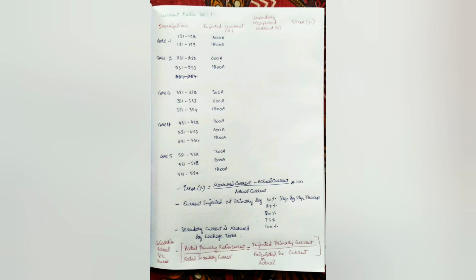So in the ratio test, for core 1 and core 2, S1 and S2 point is 600 amps maximum, and for S1 and S3 it is 1200 amps maximum. As per the connections, we will use the loading transformer for boosting the current, and then inject the current up to 1200 amps. So we inject some amps and then measure the secondary current, and that measured secondary current should be within the error percentage of your actual current level. For core 3, core 4 and core 5, as per the nameplate details: S1 and S2 300 amps, S1 and S3 600 amps, S1 and S4 1800 amps.